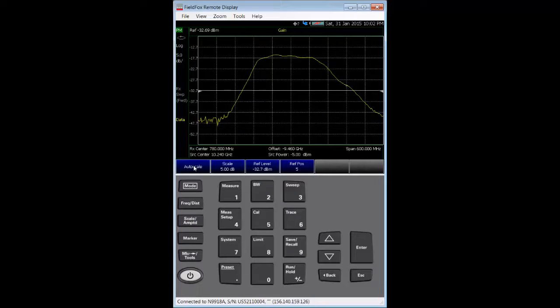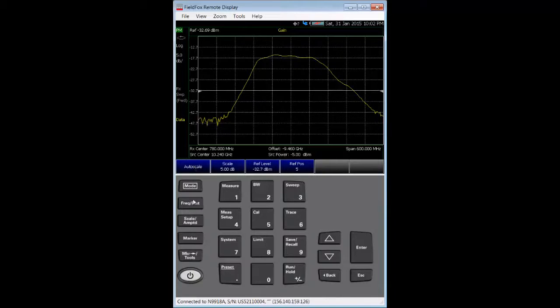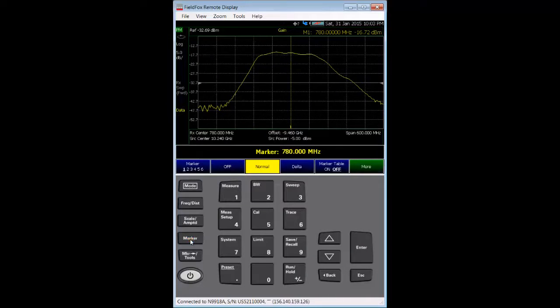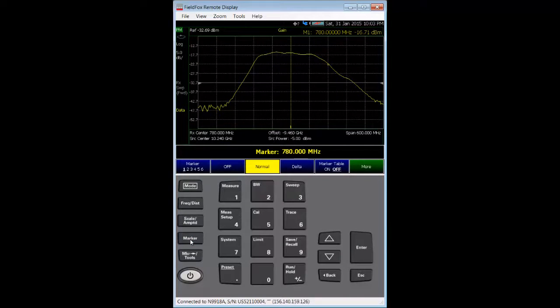I would like to see the conversion loss at the IF center frequency, so I use a marker to see this. The marker hard key shows the conversion loss, which is close to minus 17 dB, and that is what I expected to see.